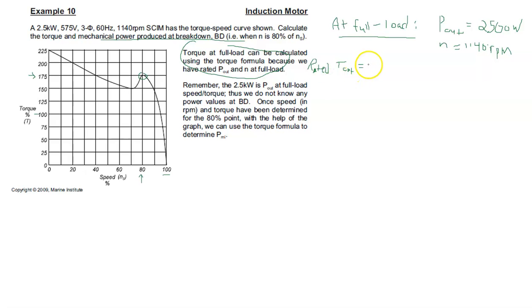...is equal to 9.55 times P out divided by N. So 9.55 multiplied by 2500 watts divided by 1140 RPMs gives us the rated torque, which is equal to 20.94 newton meters.